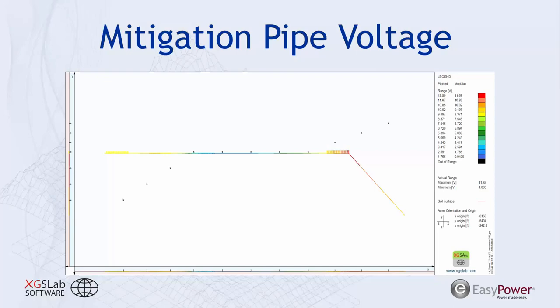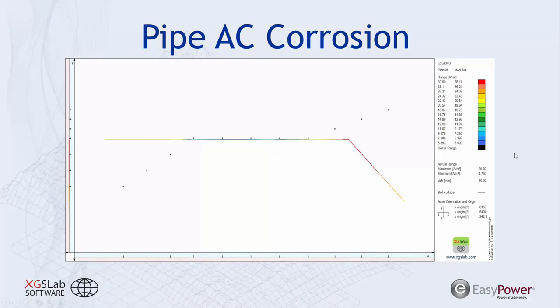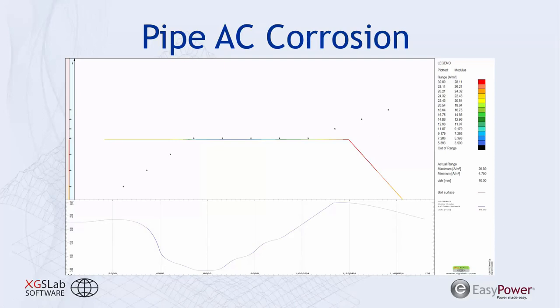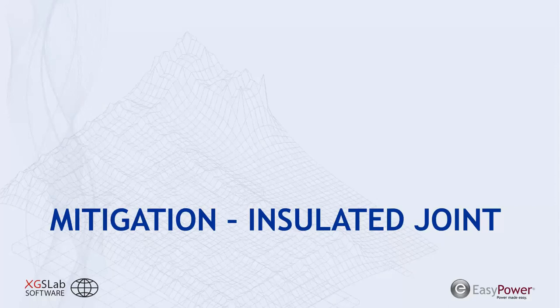So let's see what this does for the AC corrosion. Here we can see that on the pipeline we are just barely below that 30 amps per meter squared value. Here's another view of the pipeline's amps per meter squared value. And by incorporating those ground rods throughout the pipeline, we're able to keep it just below the level where we'd expect to see corrosion occurring on that pipeline. So we can also try breaking the exposure length of that pipeline to reduce how much voltage is induced upon the pipe. And we can do that using insulated joints.